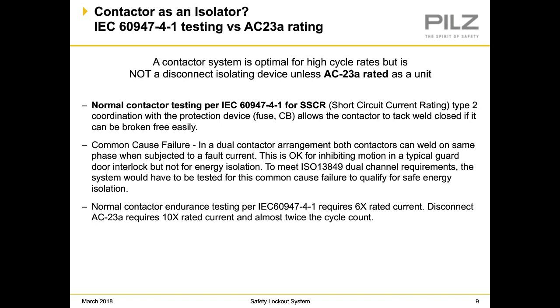To meet ISO 13849 dual channel requirements, the system would have to be tested for this common cause failure to qualify for safe energy isolation. Another fact to consider is that normal contactor endurance testing per the IEC standard requires 6 times rated current. However, disconnect AC23A requires 10 times rated current, almost twice the cycle count. So it's a lot higher standard than what contactors are normally subject to. This gets to why the system needs to be tested as a complete system, and certain contactors need to be evaluated and used with a safe lockout system.